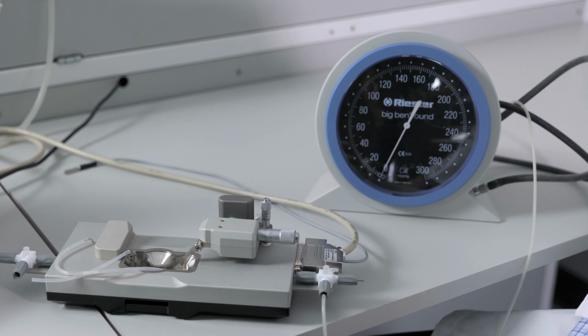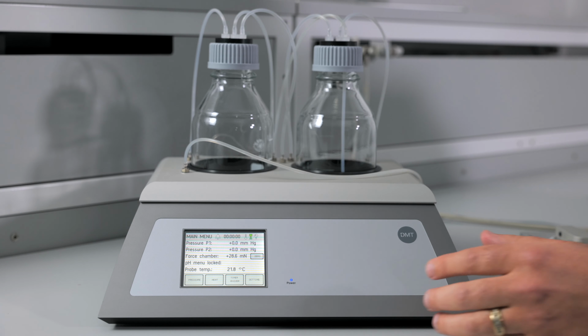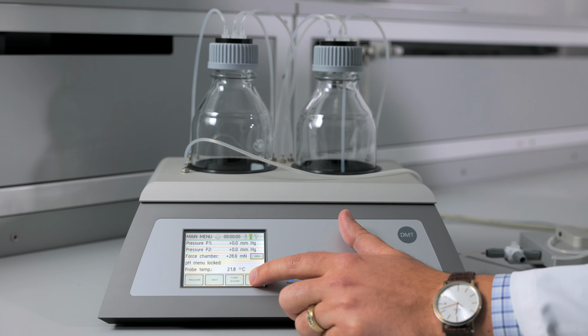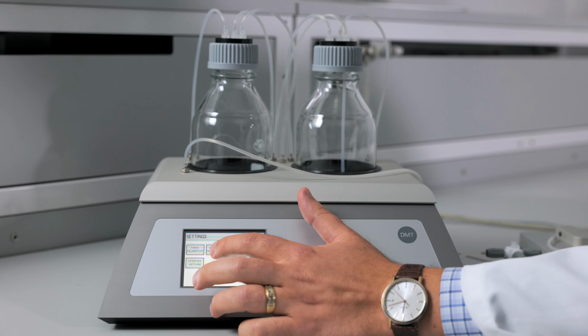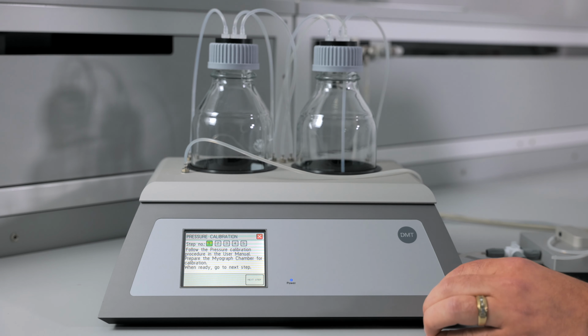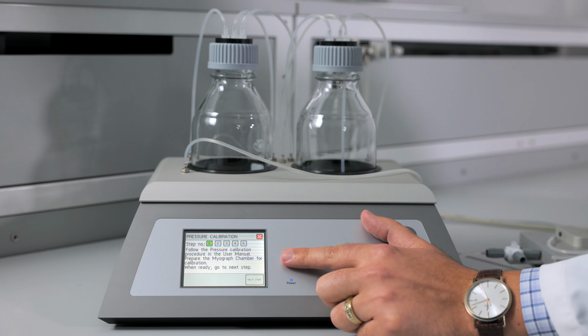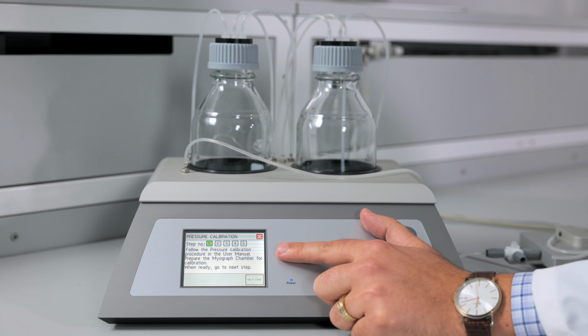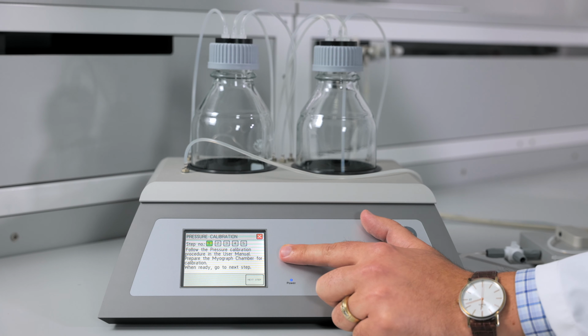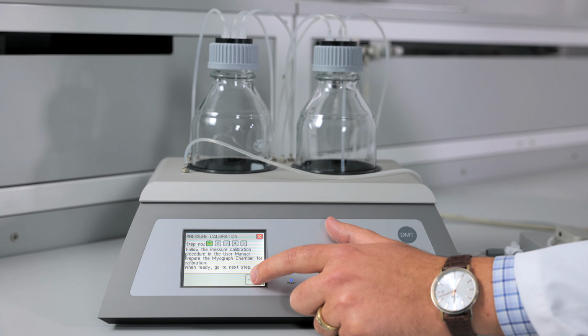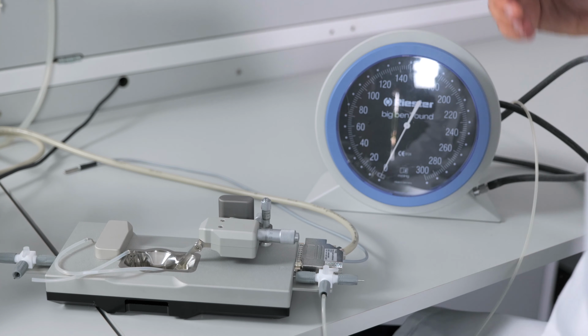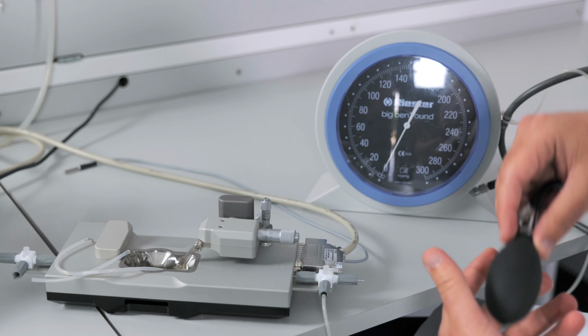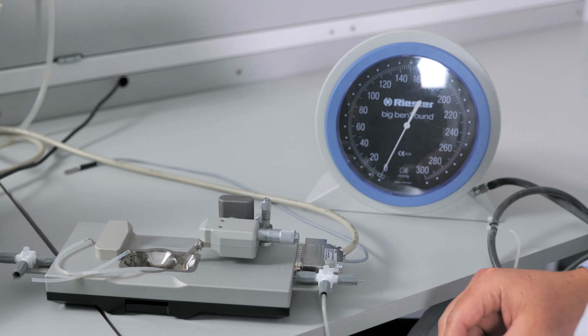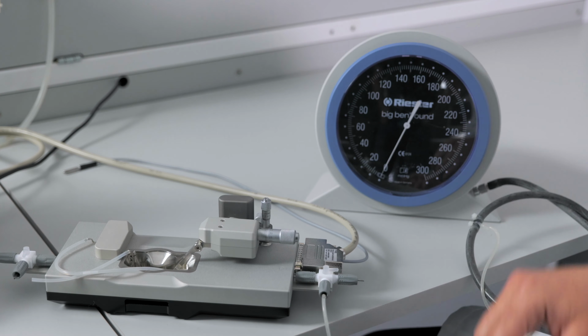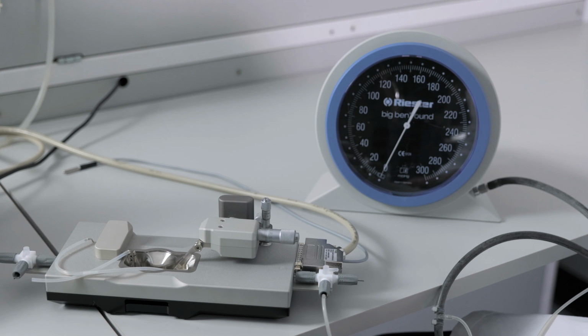We can then begin the pressure calibration. We will go into the settings menu on the interface and go to pressure calibration. This says that it's a 5-step process and you should follow the procedure in the user manual. However, instructions are also provided on the touchscreen. Select next step, which will then ask us to apply 50 millimeters of mercury pressure using the manometer. So we will add that pressure.